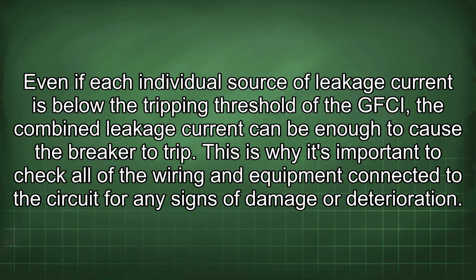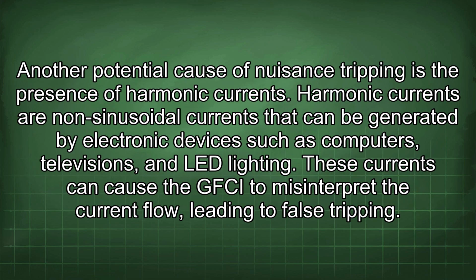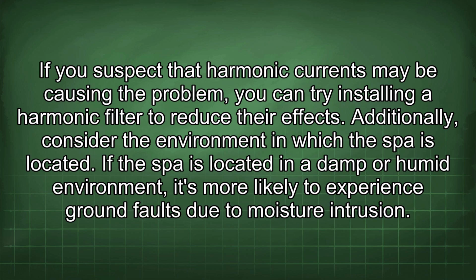This is why it's important to check all of the wiring and equipment connected to the circuit for any signs of damage or deterioration. Another potential cause of nuisance tripping is the presence of harmonic currents. Harmonic currents are non-sinusoidal currents that can be generated by electronic devices such as computers, televisions, and LED lighting. These currents can cause the GFCI to misinterpret the current flow, leading to false tripping. If you suspect that harmonic currents may be causing the problem, you can try installing a harmonic filter to reduce their effects. Additionally, consider the environment in which the spa is located.